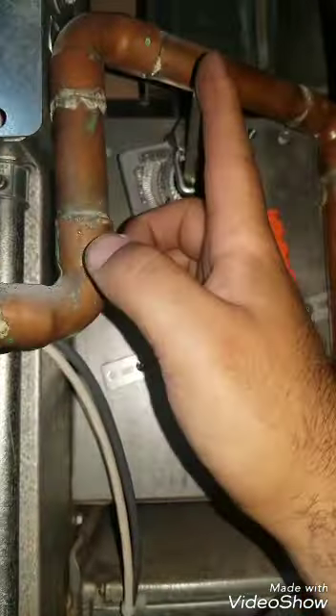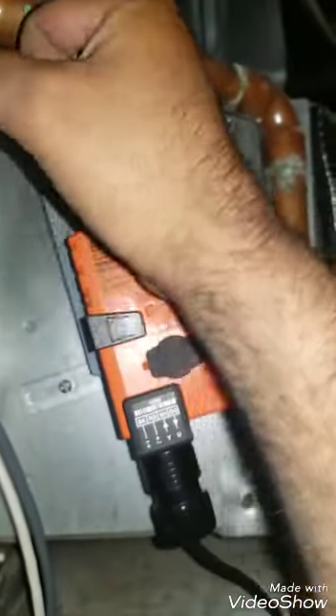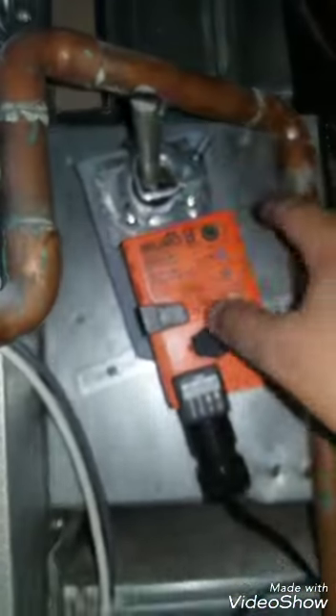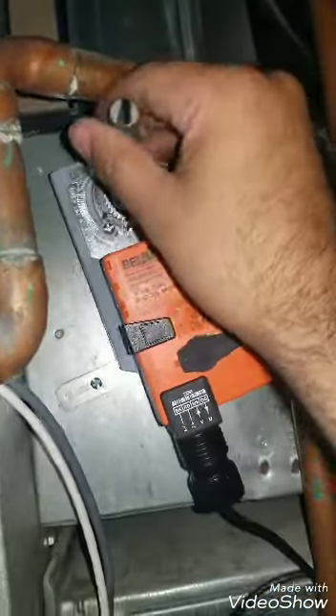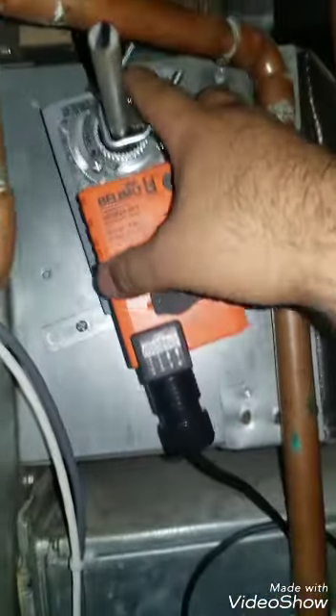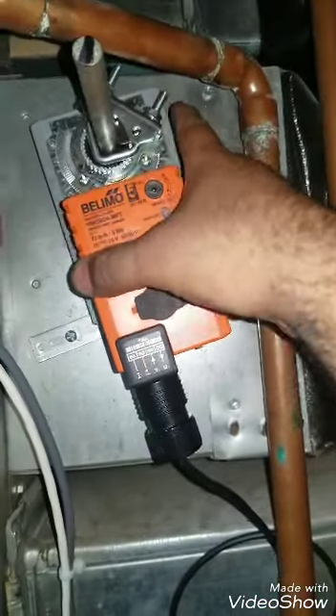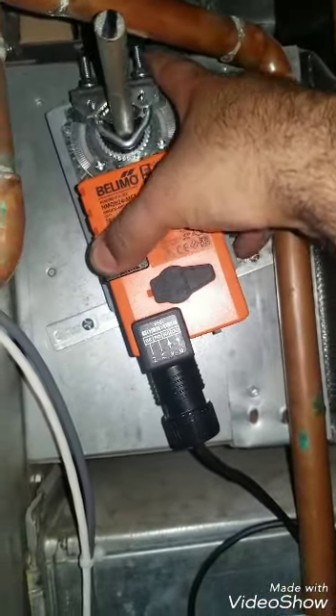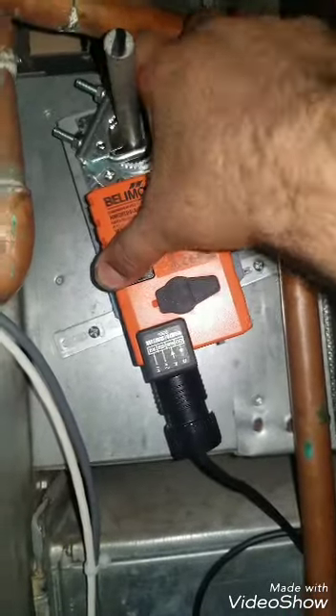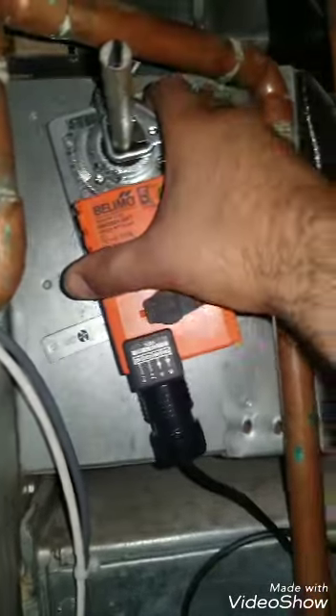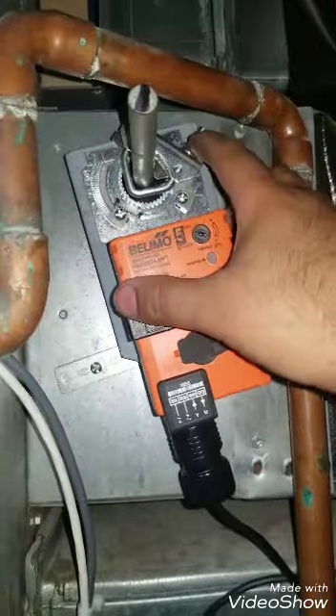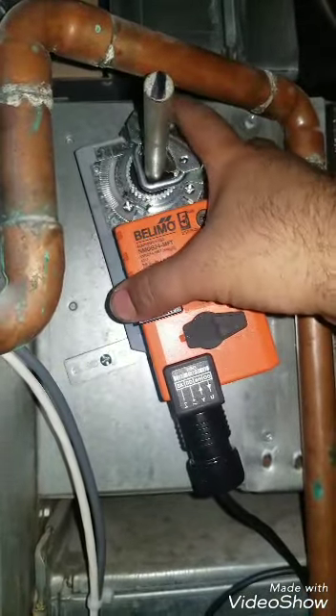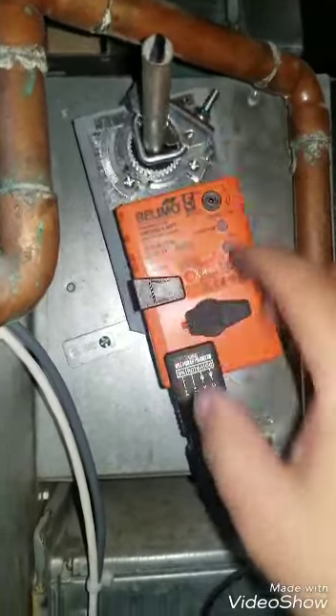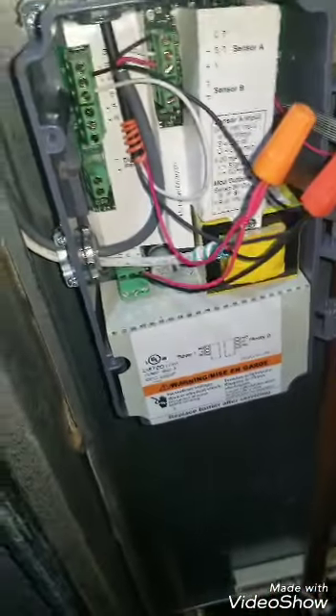So basically your damper is closed and it opens counterclockwise. So that's why if I put this in a closed position right now, 100% closed, I turn the gear like this so that when it opens, it swings the damper open. You copy? That's why I did it like that. If not, I would do it the other way. I lock these two set screws, and then do the terminations, and I'm ready to go.